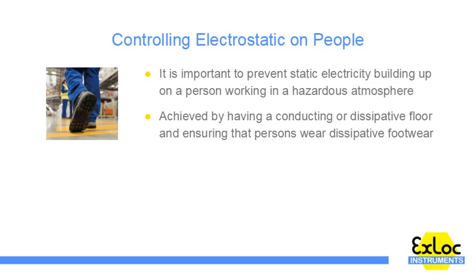Controlling electrostatic on people. Hence, it is important to prevent static electricity from building up on a person working in a hazardous atmosphere. This is best achieved by having a conducting or dissipative floor and ensuring that persons wear dissipative footwear.